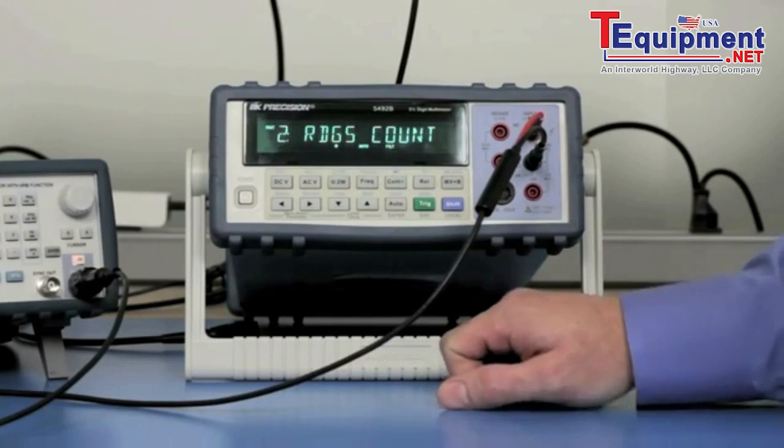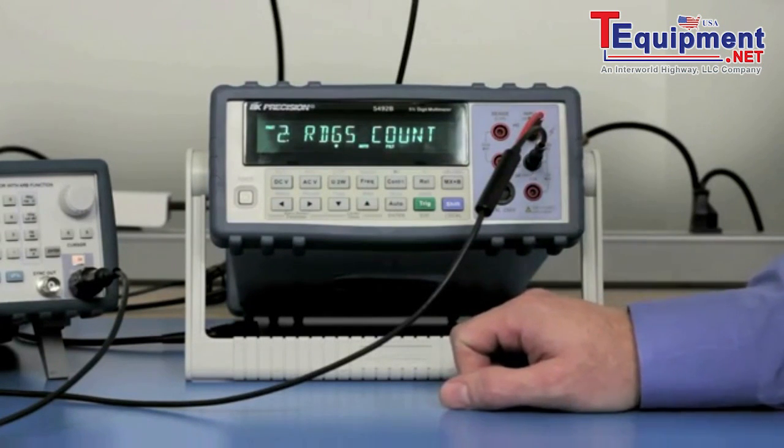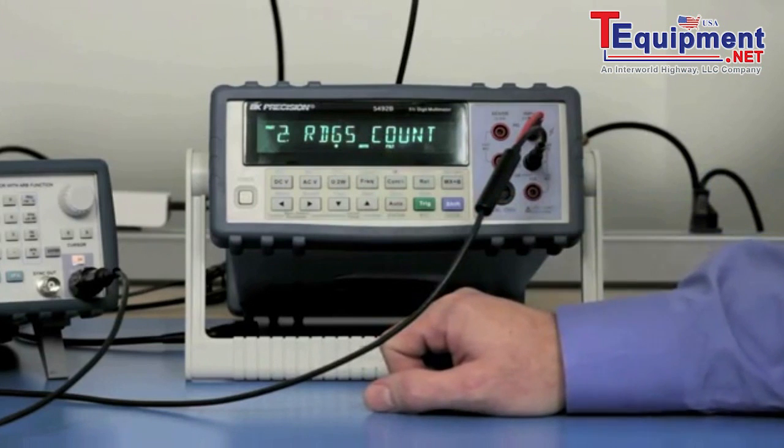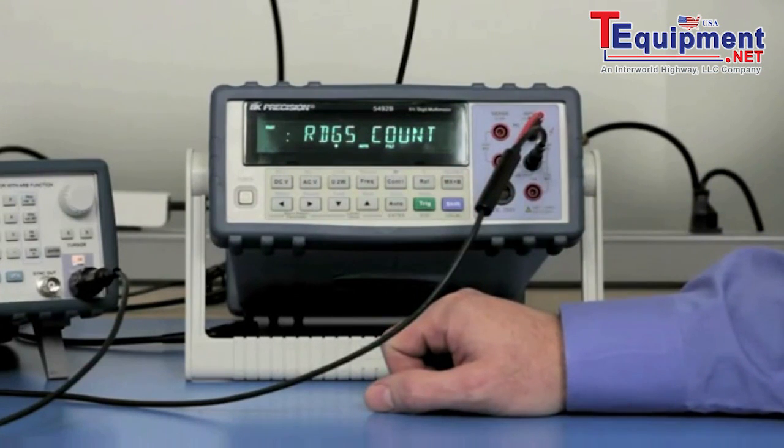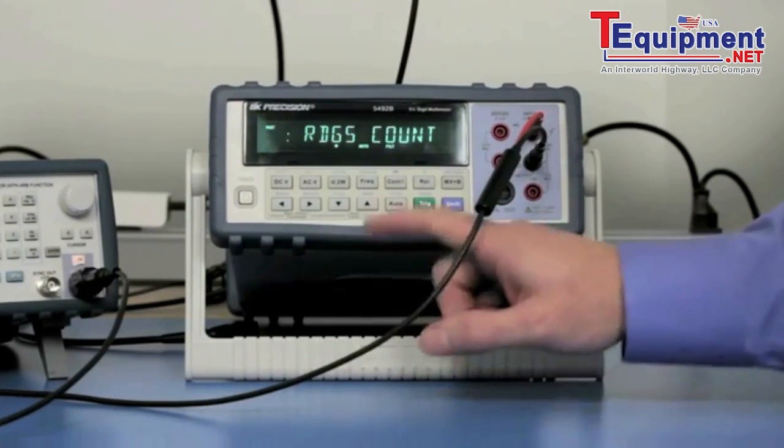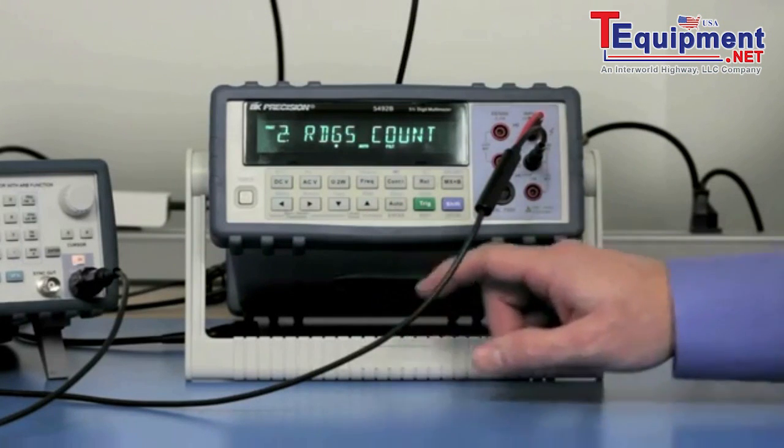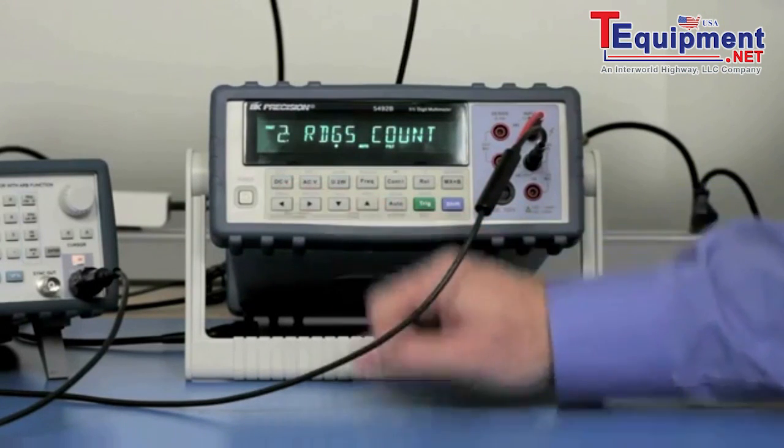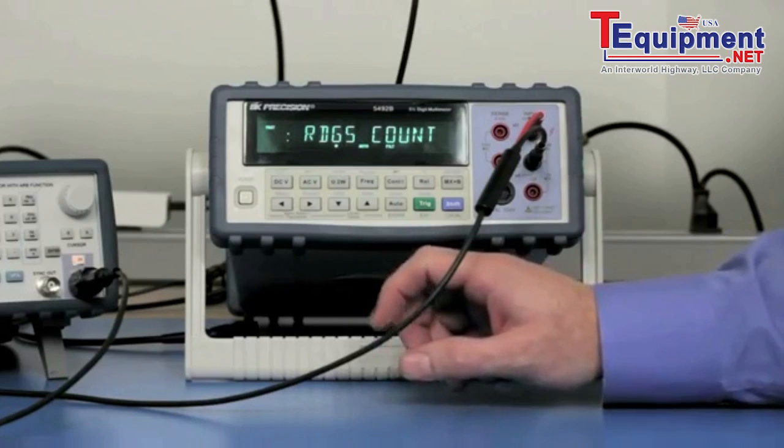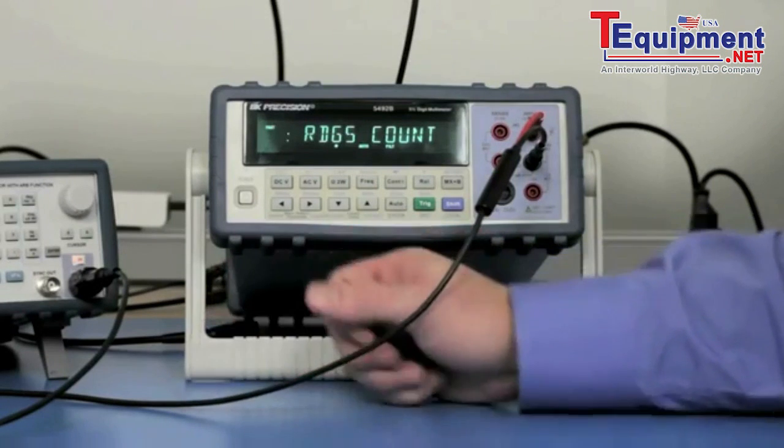Once the 5492B is in the buffer storage mode, you're going to see this little asterisk right here underneath the G telling you that it's in that mode. Now the unit is ready to go. And as soon as I press Shift-Left-Arrow, the 5492B will start to record. But before we do that, I'm going to show you how I'm going to generate the signal and what we should expect to see.